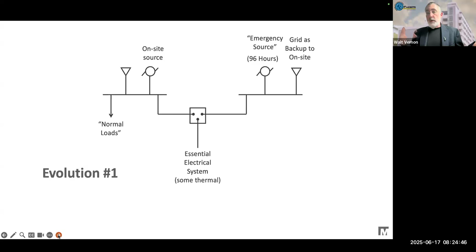A number of years ago, we put in place a change that said, yes, utility plus diesel is the gold standard, but you could also, like a lot of colleges, have your own central plant that generates your own electricity, an on-site source. The code said you could do that, and then use the utility for backup power. So our first evolution was to say, especially for emergency loads, you could have on-site or off-site on either side of the transfer switch for the emergency loads.